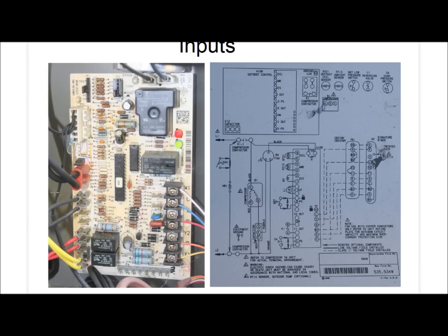All right, so let's take a look at our control inputs. When we're talking about these control inputs, just remember that they come from, look over here on the schematic, the thermostat via the air handling unit, via control wiring that was installed when the system was put in, to the control board. Do you see that? These wires are designated by the dotted lines here on the schematic diagram.